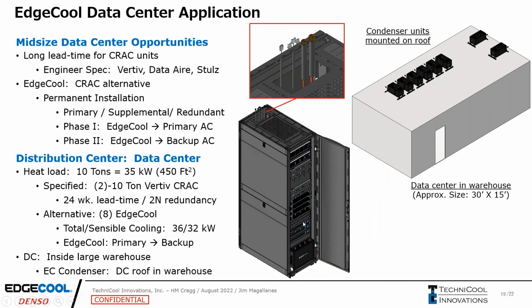One application I didn't see really coming was mid-sized data center opportunities. And this is coming as a result of supply chain issues, so long lead times for CRAC units. An engineer might specify a Vertiv, DataAire, or Stulz unit, these big CRAC units. And EdgeCool could be an alternative because of these long lead times. So for a permanent installation, we could be used as primary, supplemental, or redundant cooling.